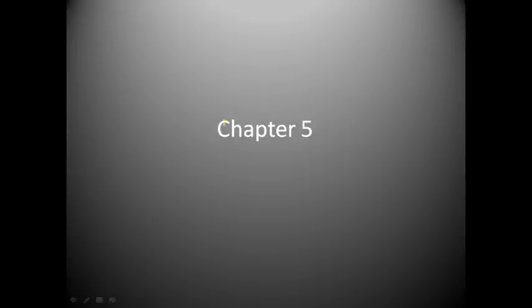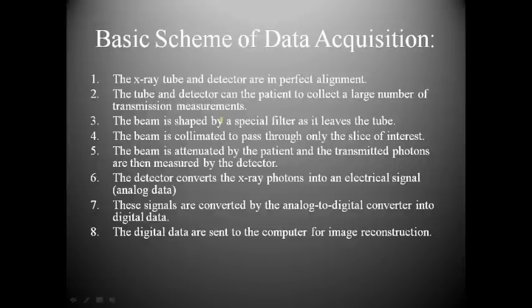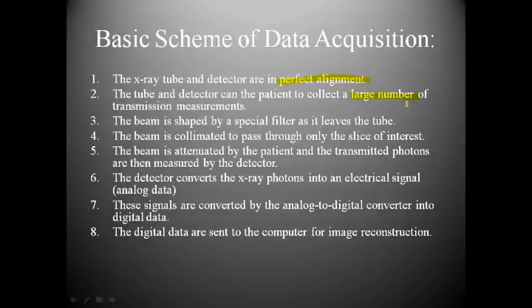Today we're going to be talking about Chapter 5, which covers basically what allows us to gain images for computer tomography. First, we're looking at the basic scheme of data acquisition. The X-ray tube and the detectors have to be in perfect alignment — any variation will lead to increased patient dosage without any noticeable gain in images. The tube and detectors scan the patient to collect a large number of transmission measurements.